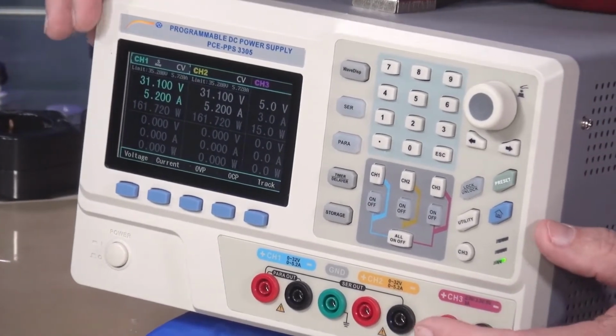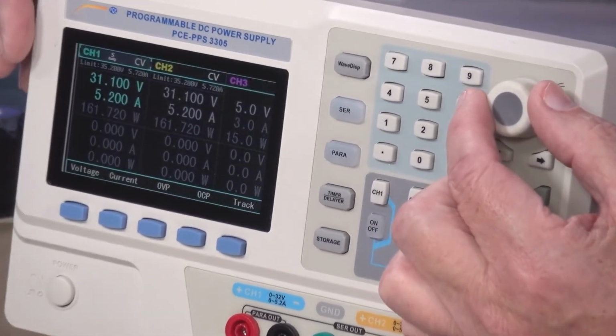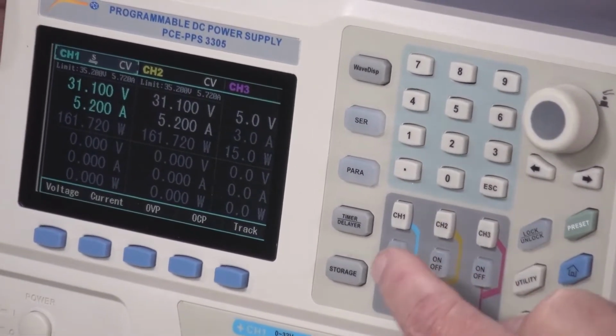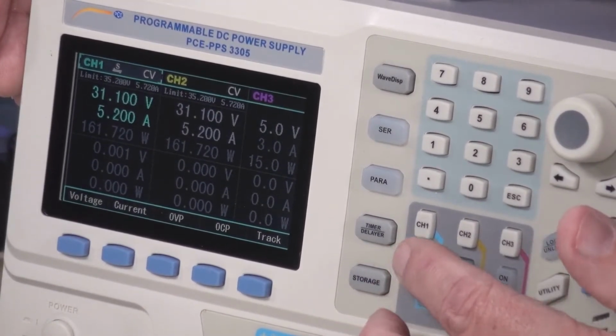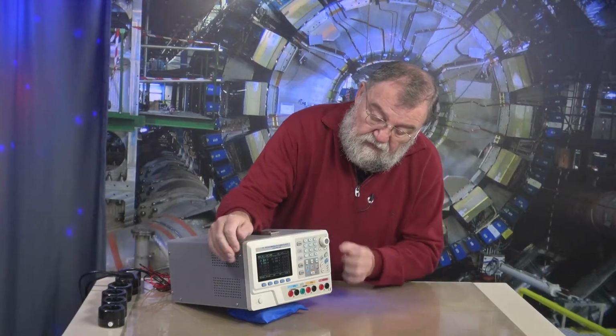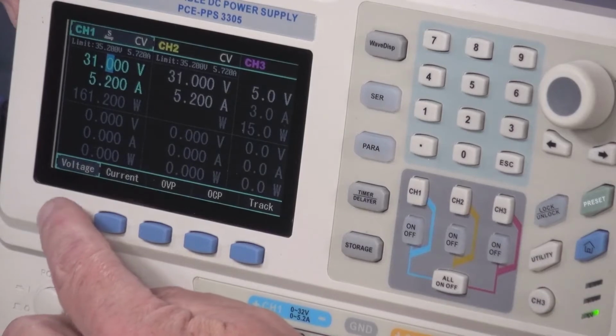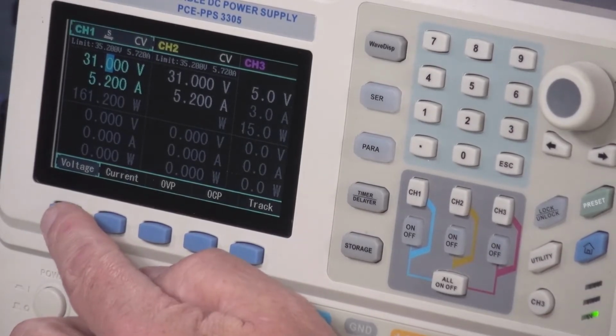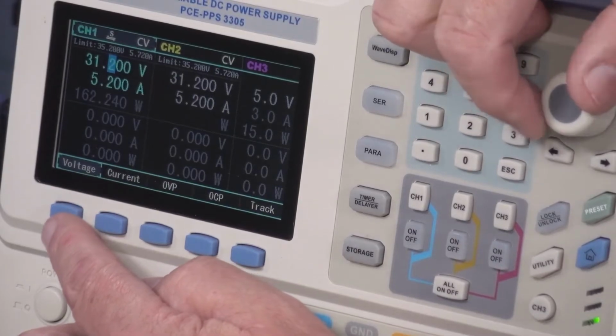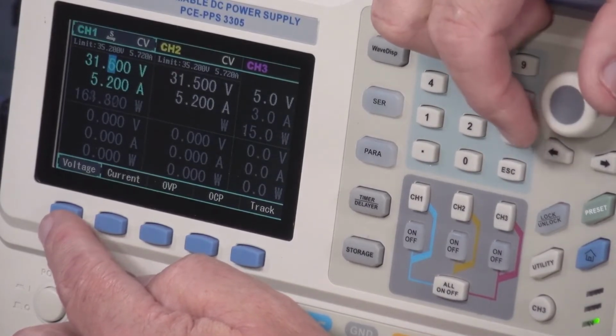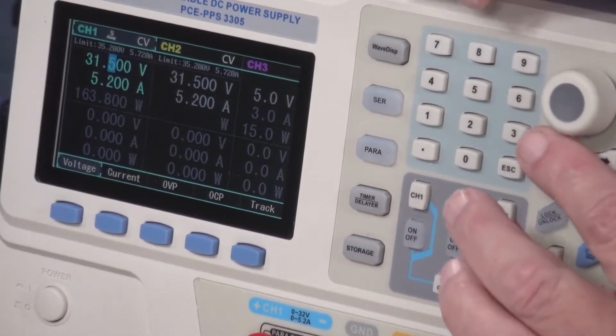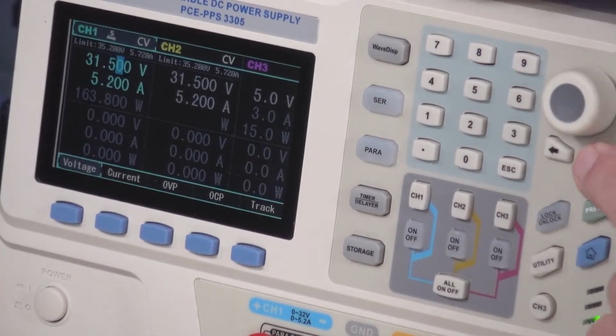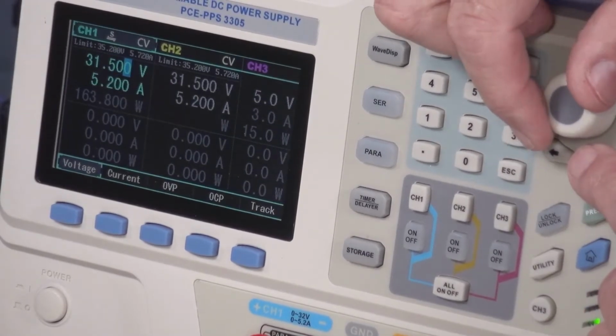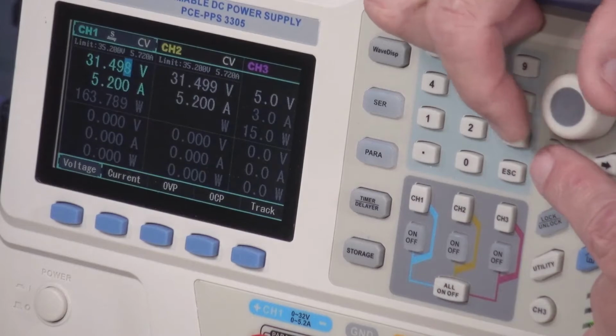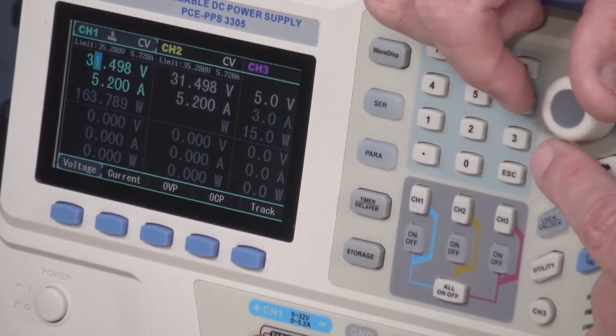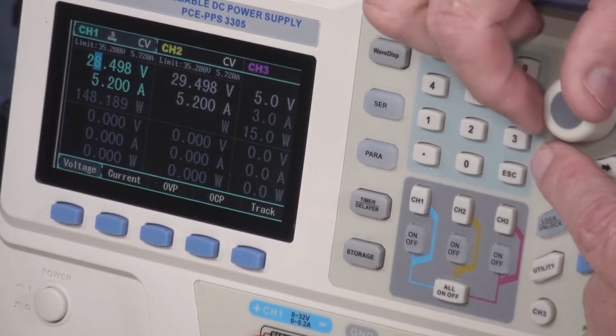Watch, I have the possibility here above to go to channel 1. Turn it on, and down here on the soft button switch to voltage. Here I have the possibility to change the voltage in 0.1 steps. I can also go to a different decimal figure, for example here, or the 1 millivolt setting, and change them. If I want to do big steps, I go here to the 1 volt setting.